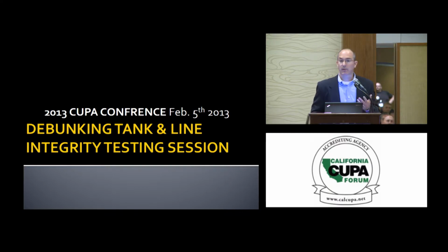A different type of probe we call a standard probe. It's a printed circuit board, which has a capacitance type measurement. It has slightly less precision, so it takes 2 hours to detect the minimum amount of water coming into the tank. And there are requirements that our technician must ensure are in place for that to be valid. Either that's if groundwater is below the bottom of the tank and there's essentially no chance of water ingress, or if there's an existing cross-section of water, or we can measure and identify that the tank is inserted in the lowest portion of the tank.